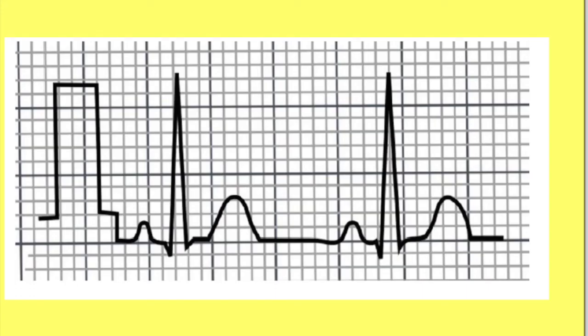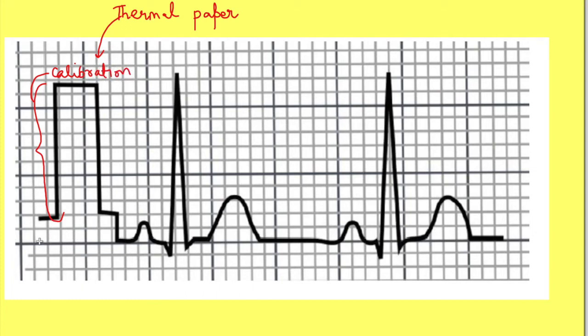Here this picture is showing a lead-2 ECG. This is the thermal paper over which ECG is recorded. This portion shows the calibration, that is the voltage recorded as some distance on paper. The standard calibration is that 1 millivolt is recorded as 1 centimeter on thermal paper. This portion is the recording of the spread of the electrical impulse in the heart, showing two electrical impulse recordings. Let us focus on the recording of one electrical activity.